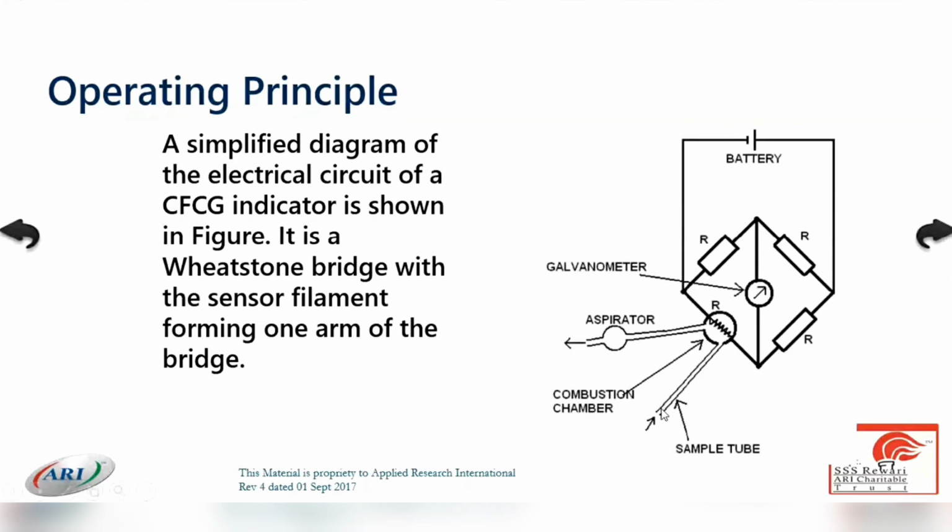The gas sample introduced in an explosive meter has hydrocarbon in LEL form and oxygen percentage more than 11%, that means in a gas-free state. When the sample of the gas comes in contact with the heated element, oxidation takes place. It further increases the temperature, the filament temperature increases more and makes the filament hotter. So as it becomes hotter, the resistance also will increase.